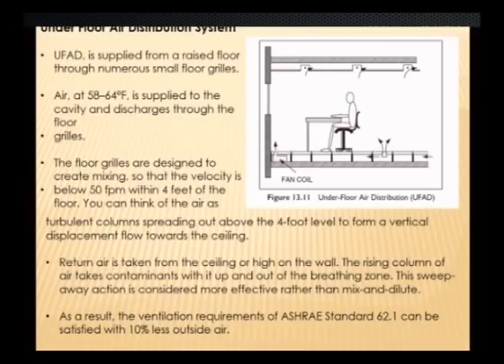The advantages of this system are that changing the layout of partitions, electrical and communication cables is very easy. In other layouts the grills and diffusers are all on the ceiling and originally designed based on the office partitions and layouts, so once you start changing or moving things, they might not be very effective. In this case, because of the floor mounted grills, we can change the layout of the partitions and other items. For buildings with high churn, like frequent layout changes, this flexibility may in itself make the added cost of the floor economically justified.